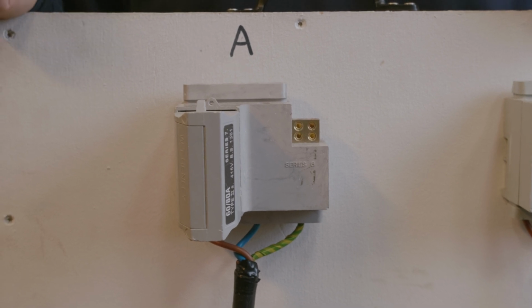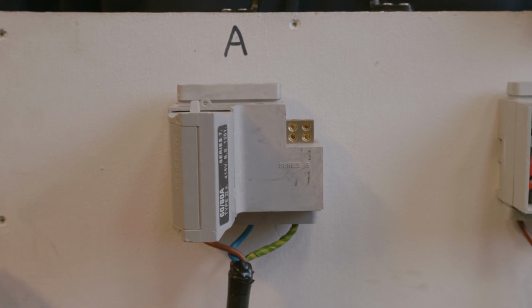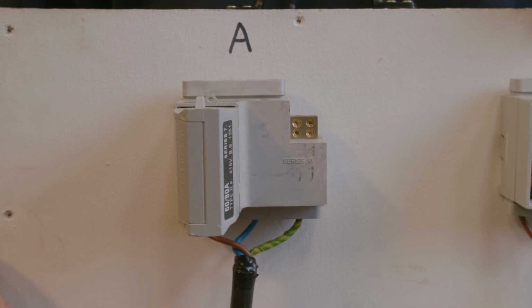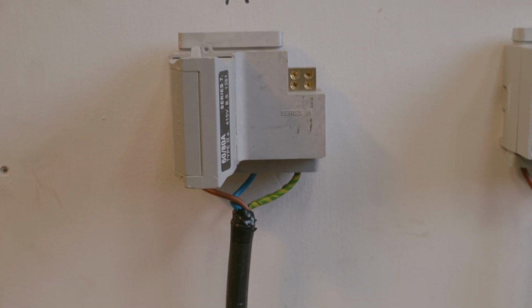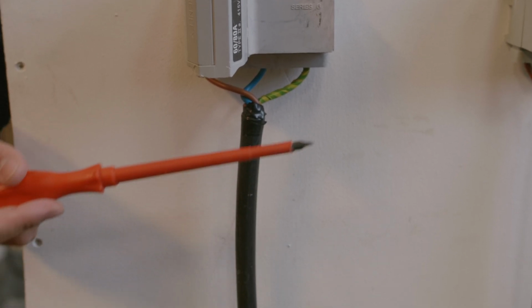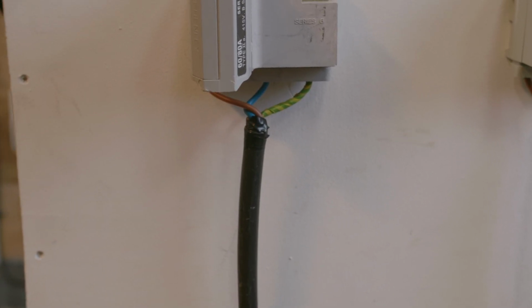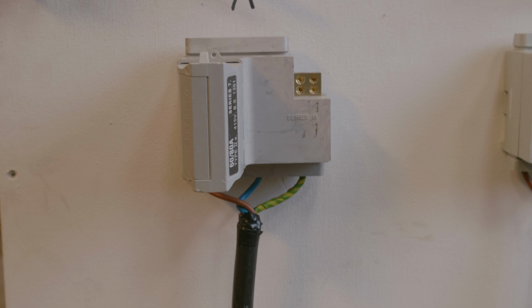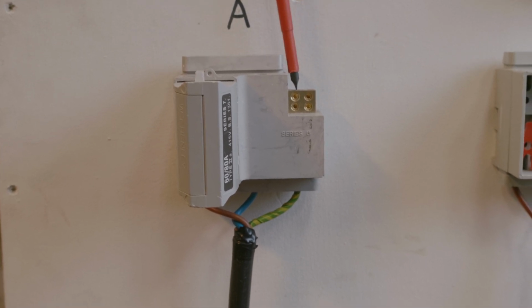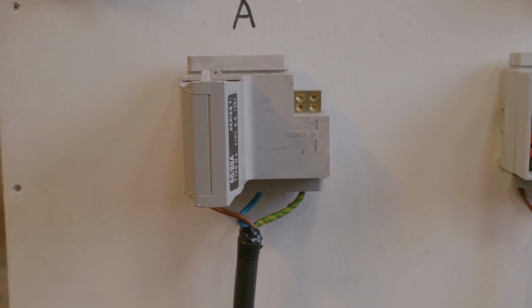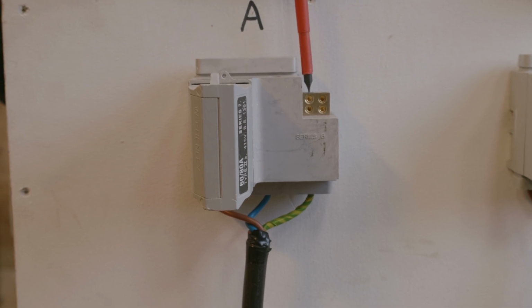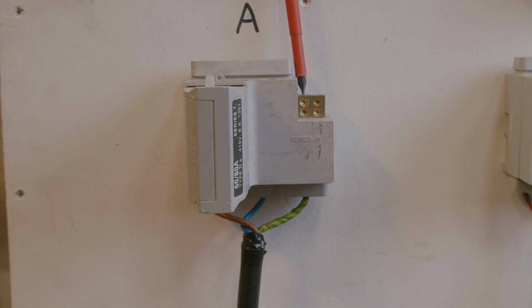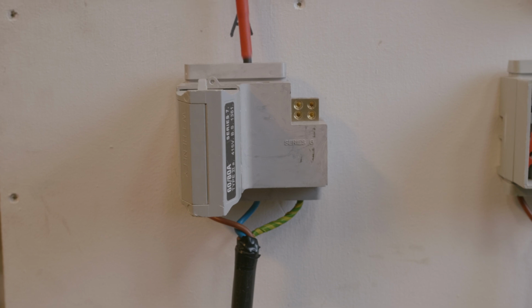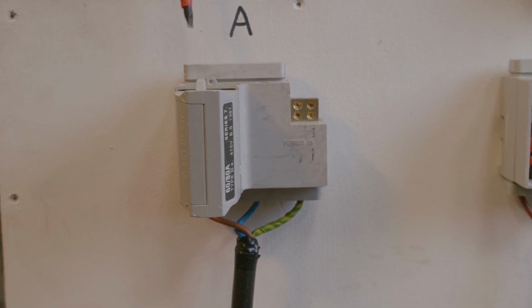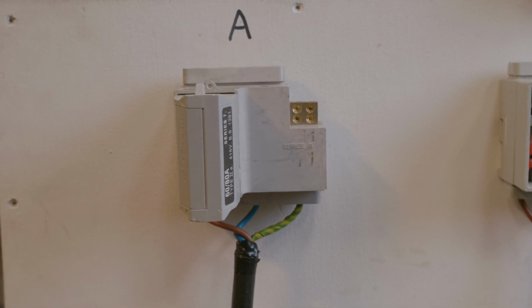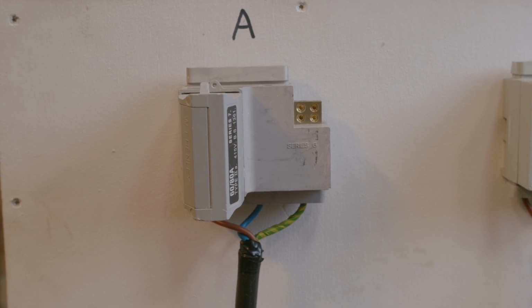For this type of cutout though, normally the bottom there would be covered with a crutch cover, so all you would see is that black supply cable coming in, so you wouldn't be able to identify that earthing arrangement as such, because you may have an earth coming out of the top of there, which would be your main earth, and you would have your neutral and you would have your line. Those conductors would be coming out, and like I say, you wouldn't normally be able to identify that until this fuse here has been removed.